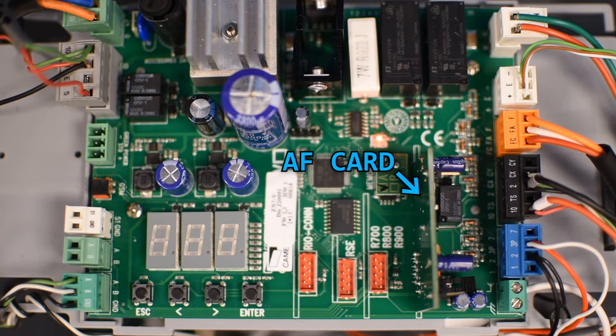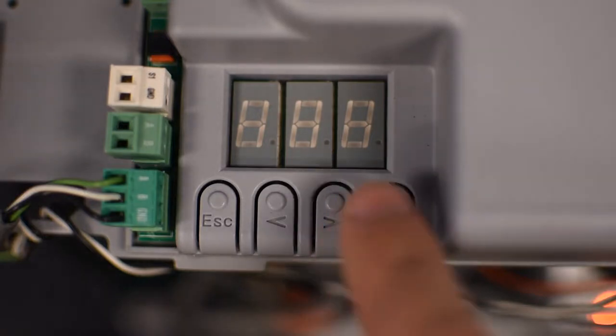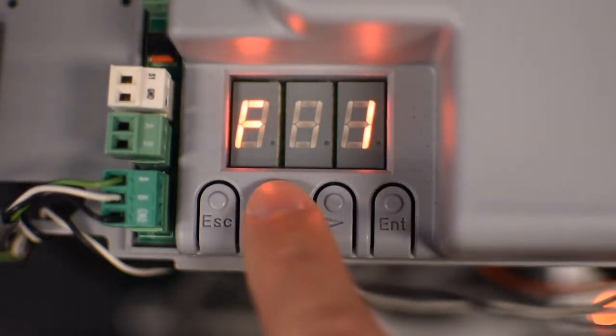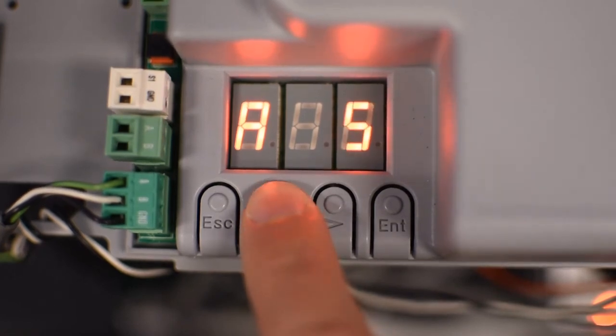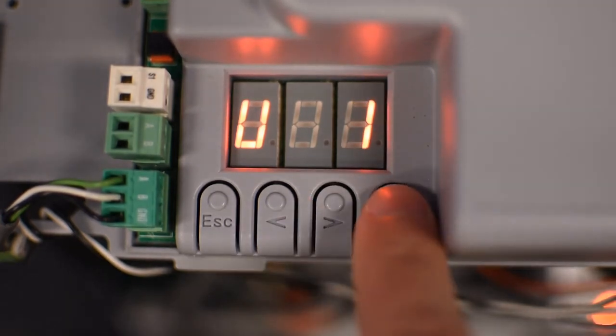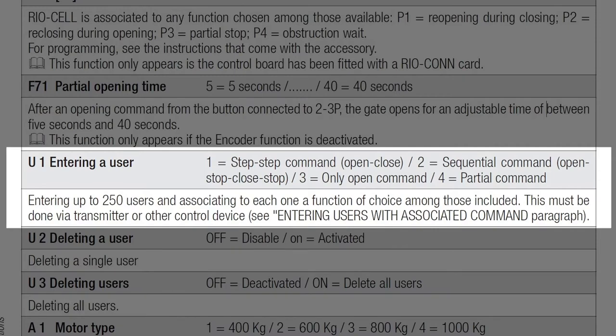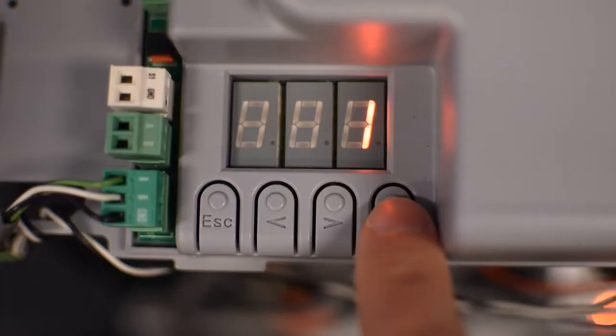If you're going to program a remote control, make sure to install the AF card in the control board. Just remember to remove the power before installing the AF card. To program a remote control, go to U1. Press Enter and it will show the number 1 indicating the command you want to assign to the button in the remote control. Select which type of command you want and press Enter.